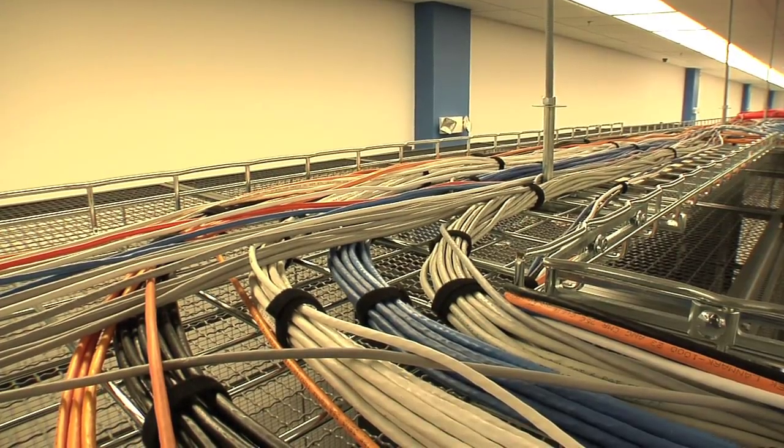That's obviously an important piece of what we do, and we put a huge emphasis on maintaining neatness. One thing, it's easier to operate when you do things the right way. I go back now I guess 12 years in the data center business, and certainly you learn as you go. We've incorporated all of that experience in this data center. We don't do very much under the floor - a lot of older data centers you'll see data cables run under the floor. We keep them on overhead racks. That helps us keep them neater, and over time we don't develop the old rat's nest that virtually all older data centers have under the floor. What that ends up doing is damming up the air. We use the raised floor as a plenum for air conditioning so we can move air where we need cool air, and when you have a lot of wires under there it tends to dam that up and you end up with hot spots.